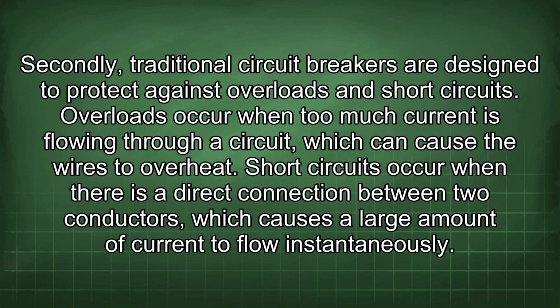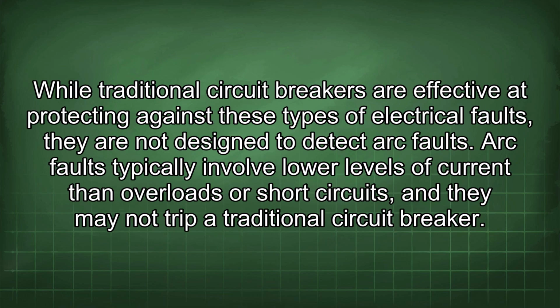Secondly, traditional circuit breakers are designed to protect against overloads and short circuits. Overloads occur when too much current is flowing through a circuit, which can cause the wires to overheat. Short circuits occur when there is a direct connection between two conductors, which causes a large amount of current to flow instantaneously. While traditional circuit breakers are effective at protecting against these types of electrical faults, they are not designed to detect arc faults. Arc faults typically involve lower levels of current than overloads or short circuits, and they may not trip a traditional circuit breaker.